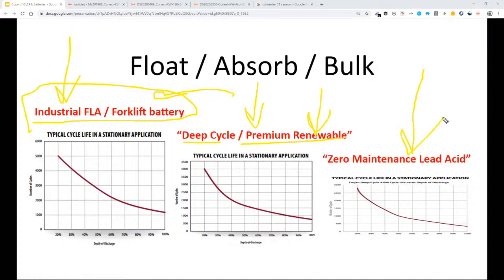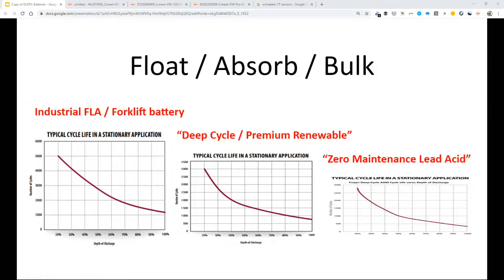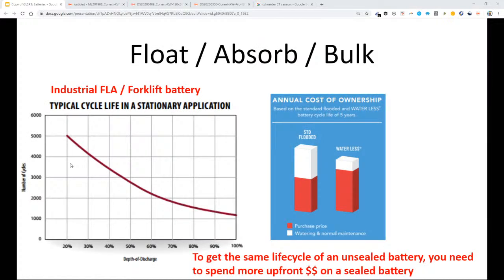And then you get to zero maintenance lead acid batteries. And those are kind of like lithium ion in that they are sealed batteries. And because they're sealed, no water escapes as water vapor. So you don't need to re-water your batteries. Well, that sounds pretty good. I don't want battery maintenance. Lithium ion battery is a sealed battery. When you look at the difference between a sealed lead acid and an unsealed lead acid, the sealed lead acid costs more money. And right here in the marketing data of the sealed battery, they're showing the purchase price of the sealed battery is more than the unsealed battery. It costs more money to make a sealed battery than an unsealed battery.